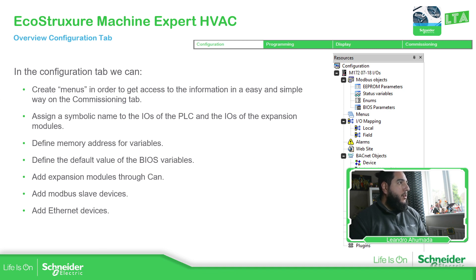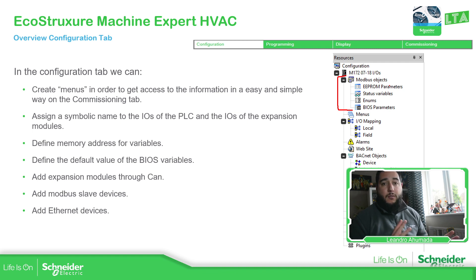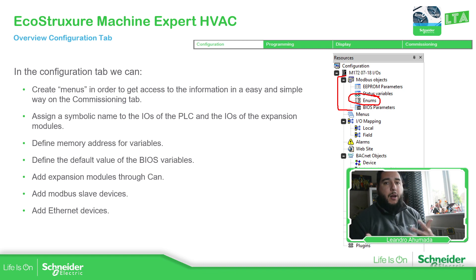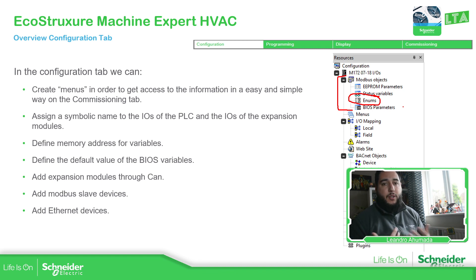If we take a look at the M172, we have Modbus objects related to EEPROM, status, and BIOS parameters. EEPROM is basically where you define all the configuration variables for the system. The status variables have some kind of indication about the process. Enums is a fancy way to see the variables — we'll probably cover that later. And the BIOS parameters are the internal system variables on the PLC that let you pre-configure the system.